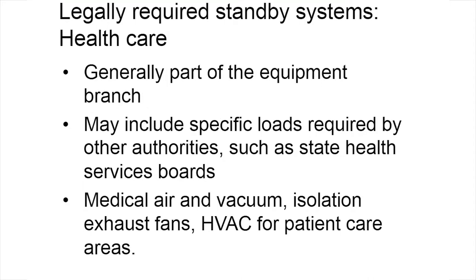Looking briefly at healthcare, legally required standby loads are typically served by the equipment branch. Some examples might be medical air and vacuum, certain exhaust fans, and certain limited heating in places that could get cold enough to cause a hazard to patients. There were a number of changes in the 2014 NEC and the 2012 NFPA 99 that affect healthcare requirements for standby power systems, and we will talk about some of those later.